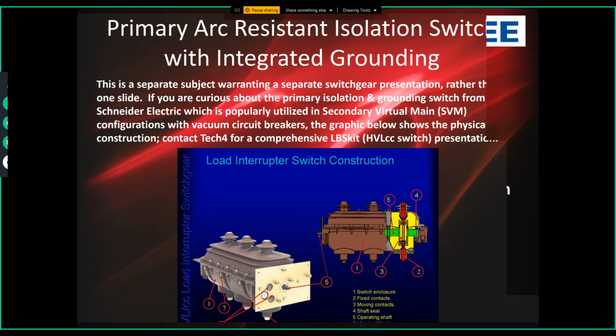But I'll tell you, prior to 2006 or 7, I didn't see hardly any of these switch over breaker. The last 4 jobs that we've been called on to design, the customer specified, large international companies, isolation and grounding switch over breaker, because again, they want to do away with the danger, the discomfort and the time necessary to attach manual ground cables. They want integrated grounding devices, such as what is shown in this load interrupter switch construction. Integrated grounding is a wonderful idea. It should be adopted on a wider basis, in my opinion.